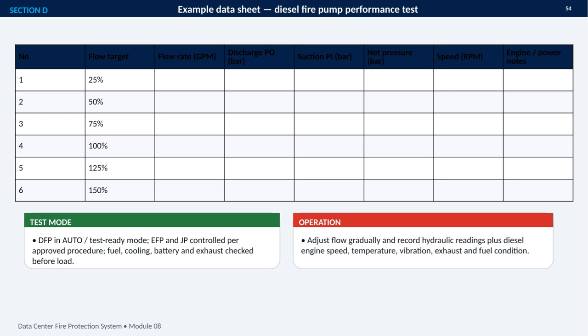against the approved requirements. Before applying load, the diesel fire pump should be in automatic, test-ready mode. The electric fire pump and jockey pump are controlled according to the approved procedure, while fuel, cooling, batteries, and exhaust are checked in advance. During the test, flow should be increased gradually rather than changed abruptly. At each target, record the hydraulic readings together with diesel engine speed, temperature, vibration, exhaust condition, and fuel condition. This makes the sheet more than a pressure log.